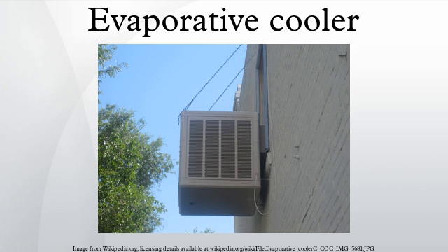Because evaporative coolers perform best in dry conditions, they are widely used and most effective in arid, desert regions such as the southwestern USA and northern Mexico. The same equation indicates why evaporative coolers are of limited use in highly humid environments. For example, a hot August day in Tokyo may be 30 degrees, 85% relative humidity, 1005 hectopascals pressure. This gives dew point 27.2 degrees and wet bulb temperature 27.88 degrees.